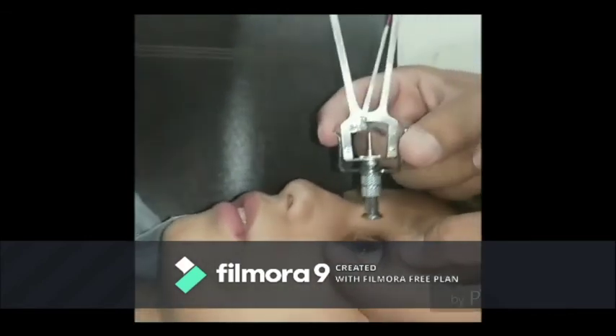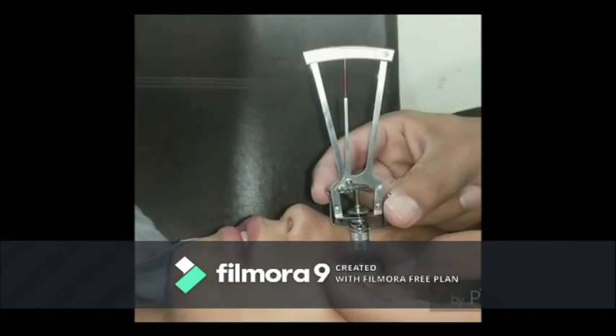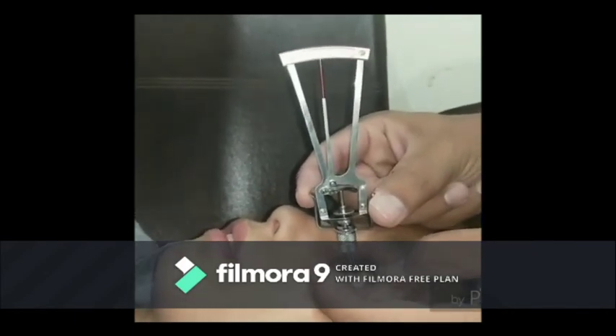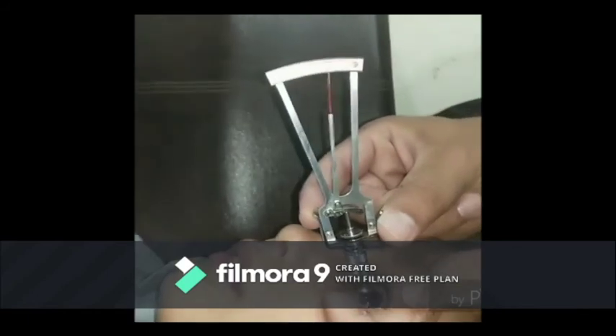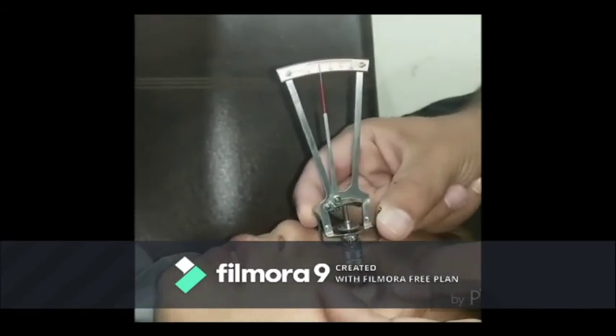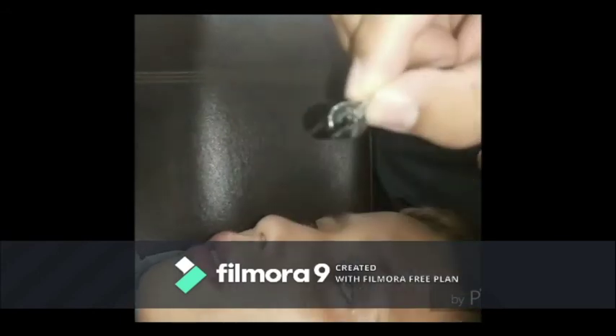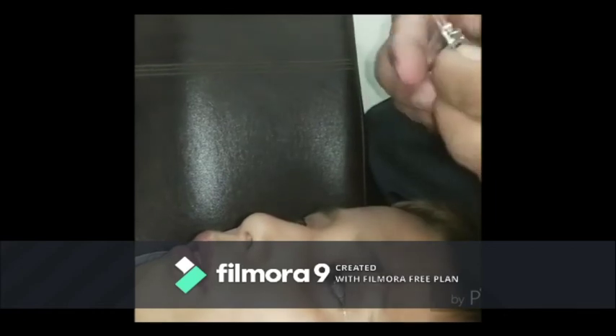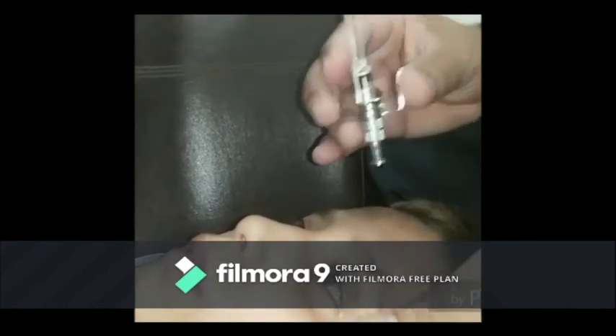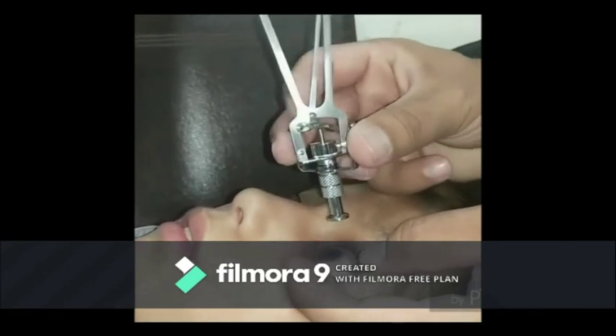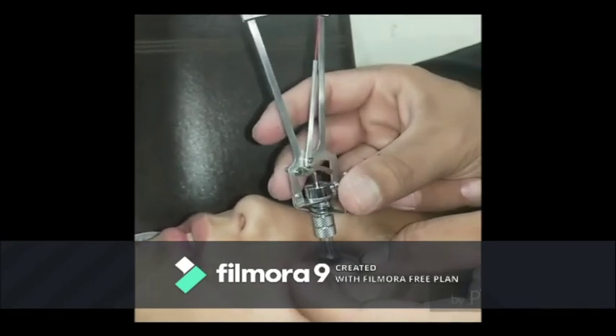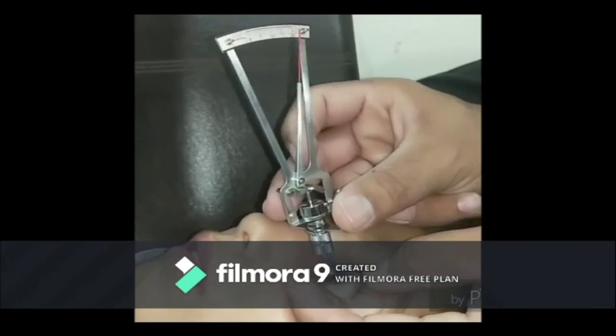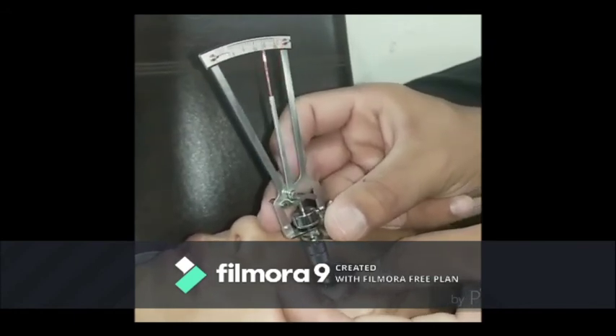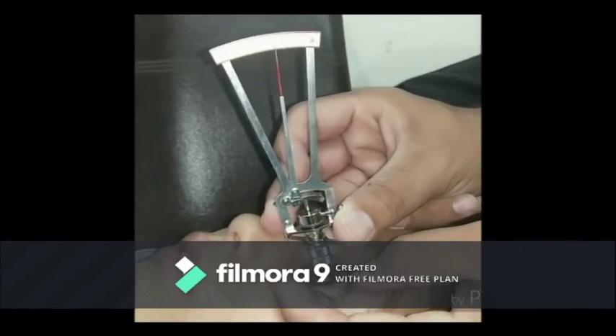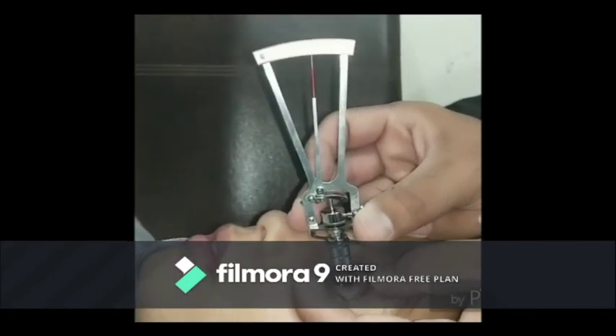Using the index finger and thumb, we can open the upper and lower eyelids. Then we put the footplate in the center of the cornea. We can do this 2 to 3 times to ensure we are getting the correct measurement. Here, the examiner tries putting a 10-gram weight on the plunger of the tonometer. Then he checks the left eye again by putting the footplate on the cornea. Watch the examiner's hands as he does it 2 to 3 times to measure accurately.